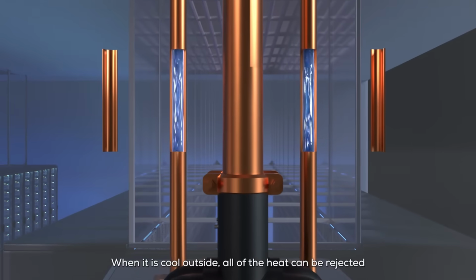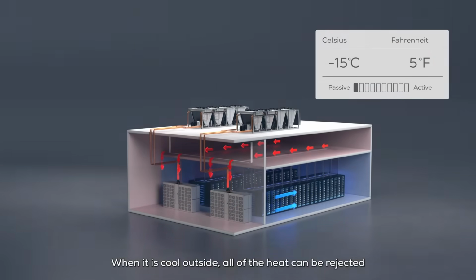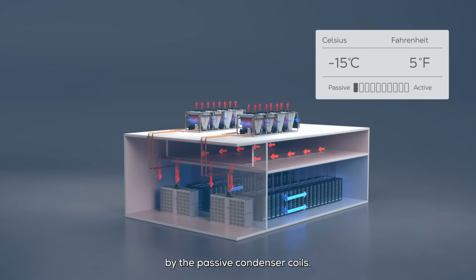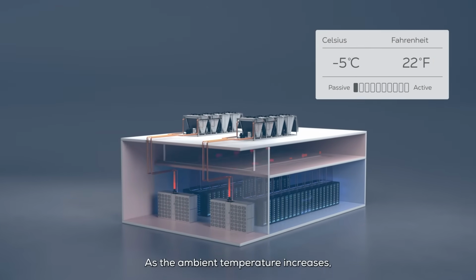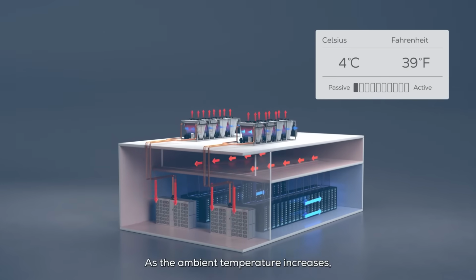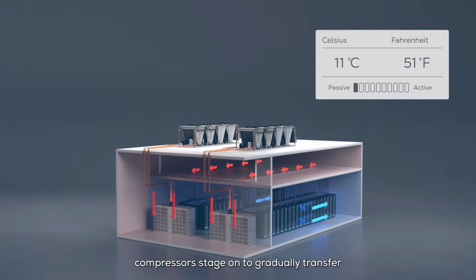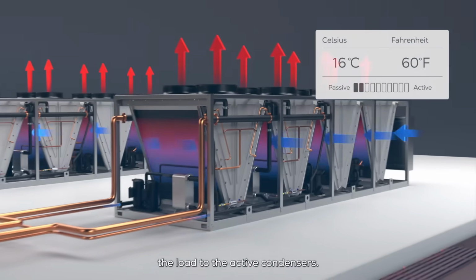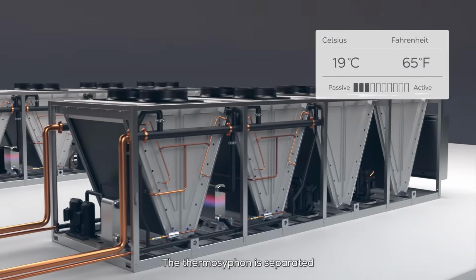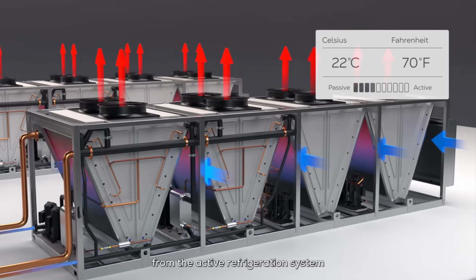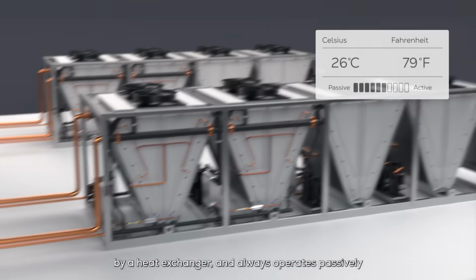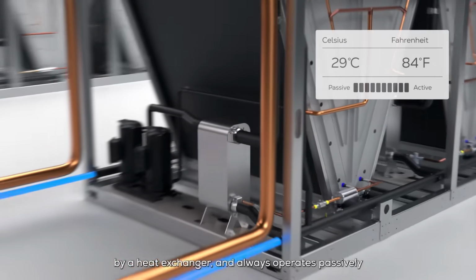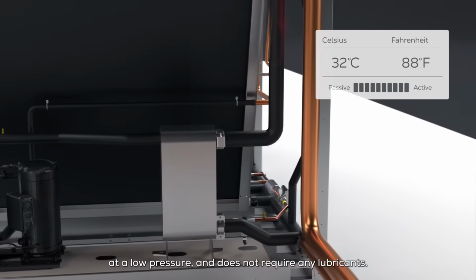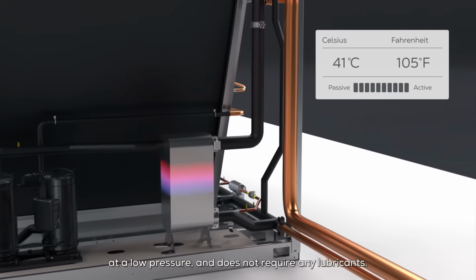When it is cool outside, all of the heat can be rejected from the thermosiphon loop by the passive condenser coils. As the ambient temperature increases, compressors stage on to gradually transfer the load to the active condensers. The thermosiphon is separated from the active refrigeration system by a heat exchanger, and always operates passively at a low pressure and does not require any lubricants.